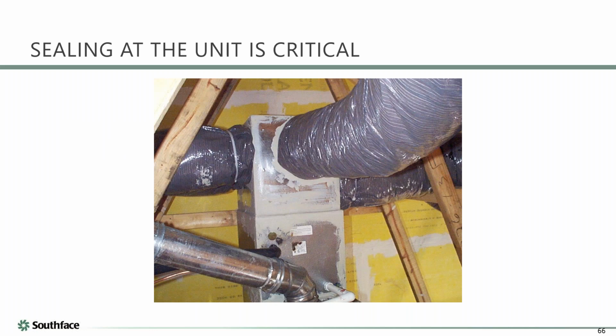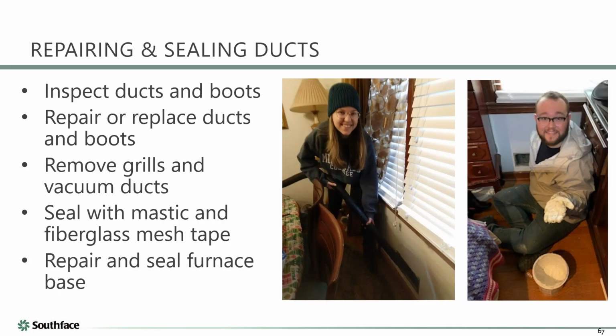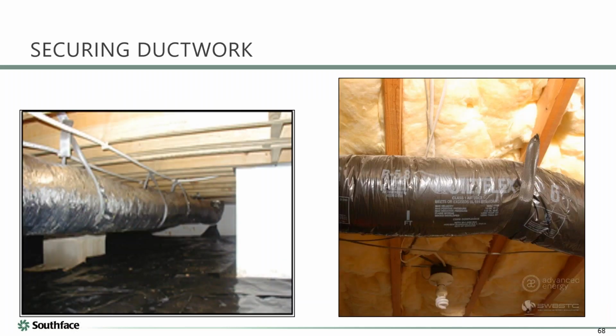Right there at the blower. So even a small leak at the air handling unit is a big energy penalty. On existing homes, we recommend you pull the registers, vacuum out the inside, reach in as far as you can with mastic and a glove, and start sealing and work your way out.